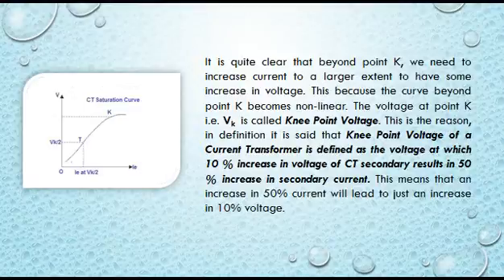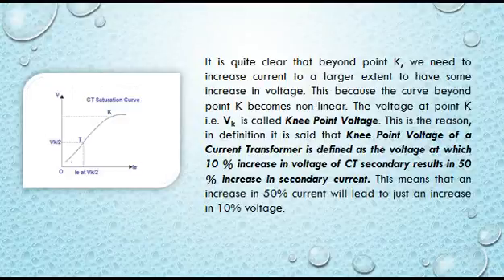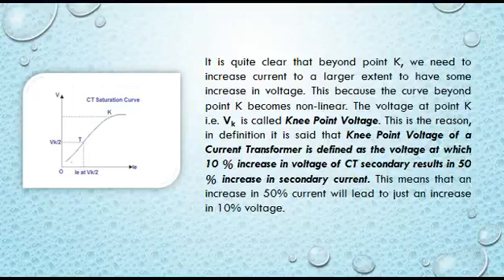By IEC definition, the knee point voltage of a current transformer is defined as the voltage at which a 10% increase in CT secondary voltage results in a 50% increase in secondary current. In other words, beyond point K, an increase of 50% in current will lead to just a 10% increase in voltage.